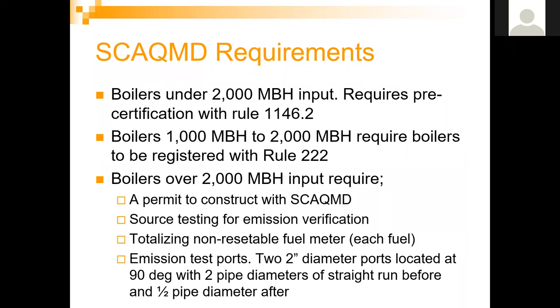Boilers from 1,000 to 2,000 MBH: South Coast AQMD requires these boilers to be registered under Rule 222. They don't require a permit as long as they're pre-certified, but they require registration. This is a simple one-sheet form filled out and sent to the district with a nominal fee, letting the air district know you have that boiler installed at your facility. You need to fill one out for every appliance being installed.